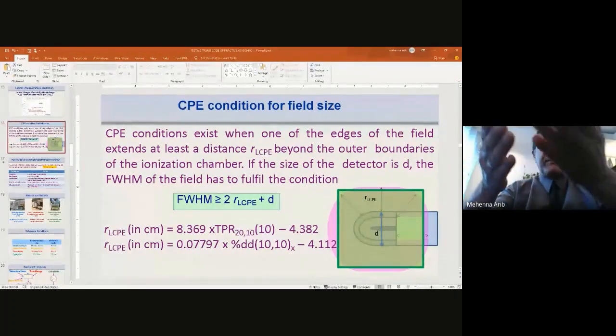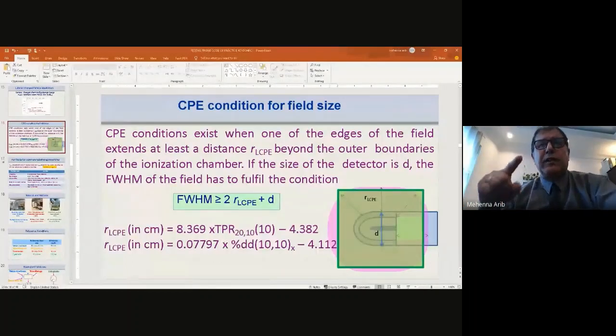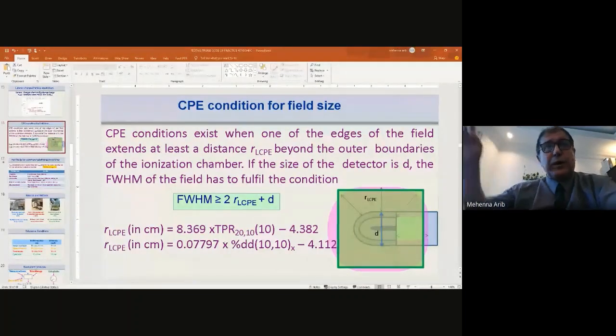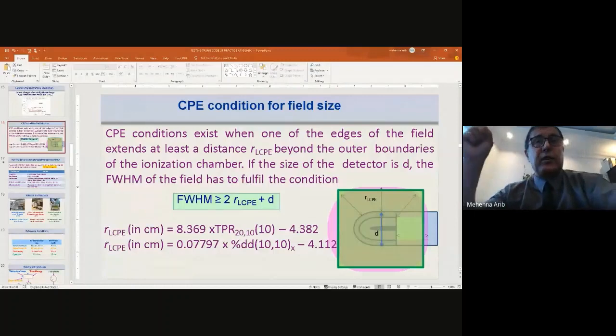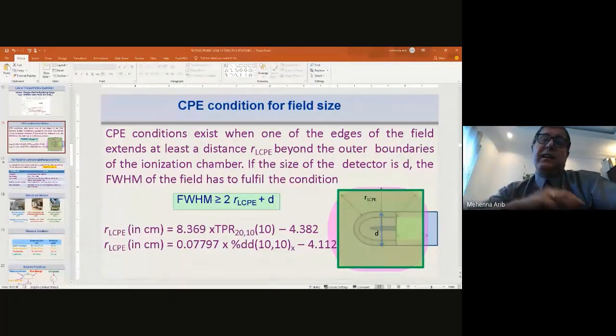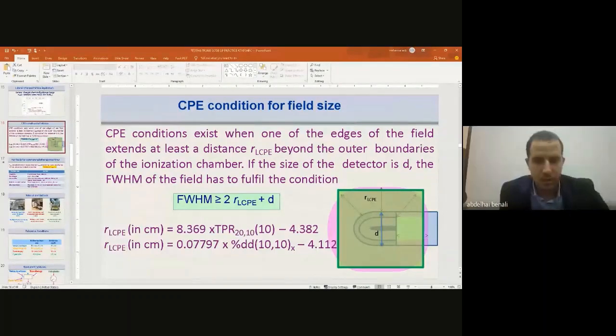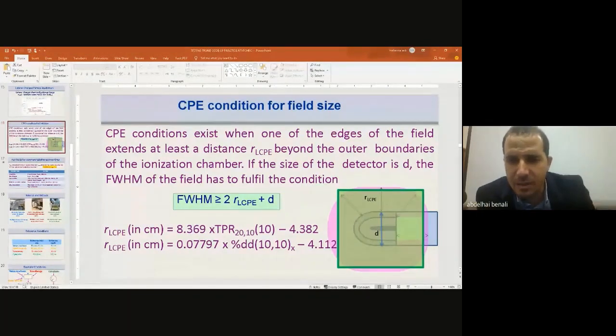So you have a problem of small fields. You need to measure the dose for the small fields. That's why you have to decrease the field size from 10 by 10 down to 5 millimeter by 5 millimeter. Yes, thank you. Second question is how you calculate the difference. What's the rule? The difference is equal to the measurement value minus the Monte Carlo value divided by the measurement value times 100%.